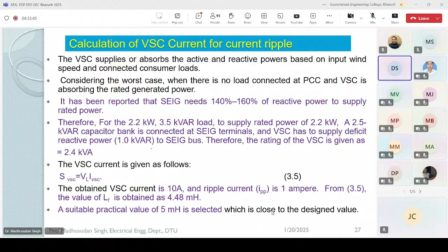This is how you decide the rating of all these components. These formulas are standard, and with them you can find the voltage at the DC link, because to ensure PWM control of the inverters, you need the battery side voltage higher than the peak of your AC side.